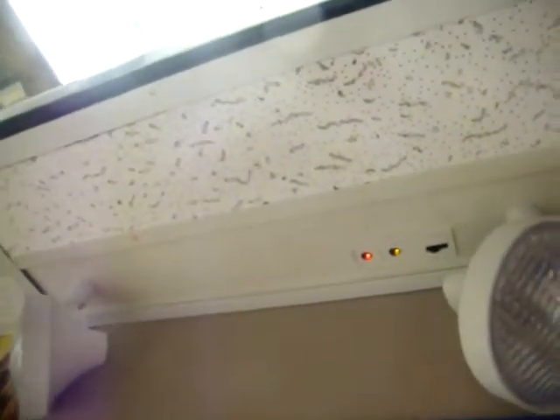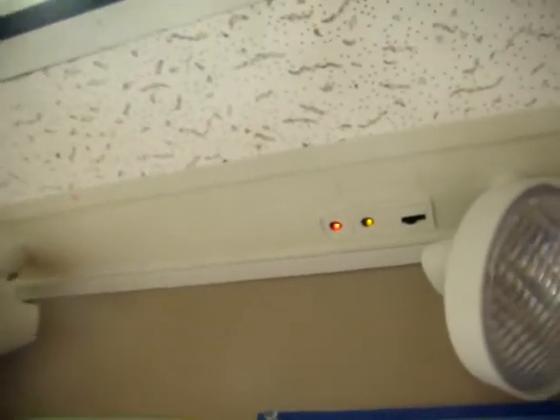There's a security camera and then up here I've got an Emergi-Lite ceiling mount unit. I did a first take of this video a little while ago — I already tested it and that's why the red charge light's on. The battery is still good. Continuing on — this is the other fixture that's got the emergency ballast in it. There's the charging light for that one.